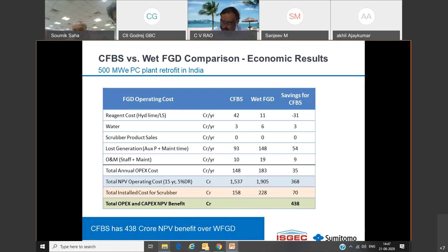Another thing is this semi-dry FGD can capture SO2, SO3, HCl, HF, Hg, PM, and all other constituents. Then high fuel flexibility, though this is there for wet FGD also. And another thing is that very fine particles can be captured because bags are there in this semi-dry FGD. Gypsum is not generated. A byproduct is generated, which is much lower in quantity than the gypsum quantity.